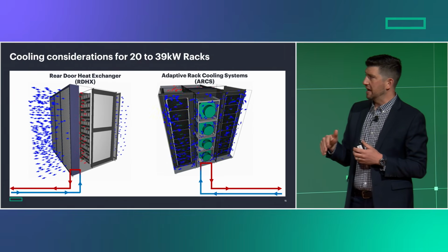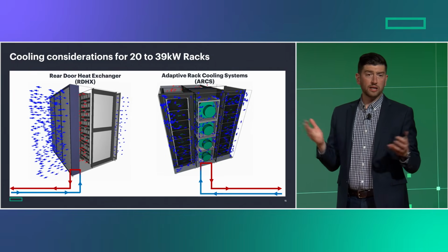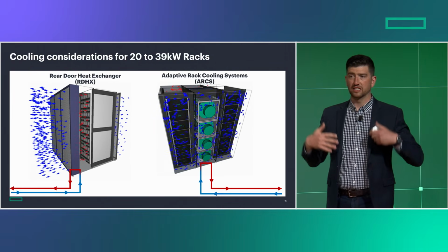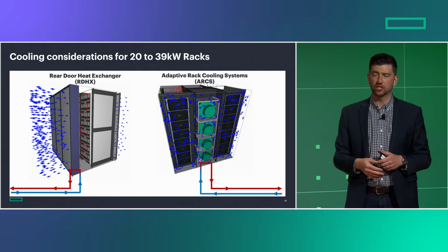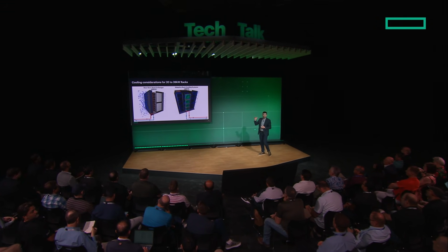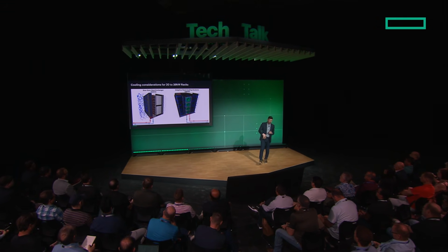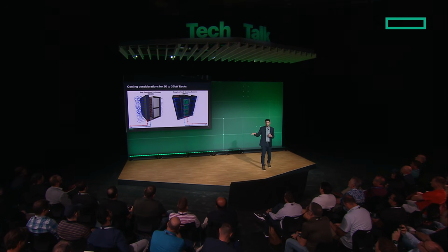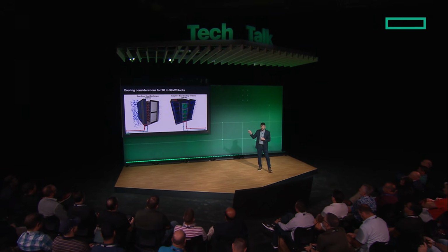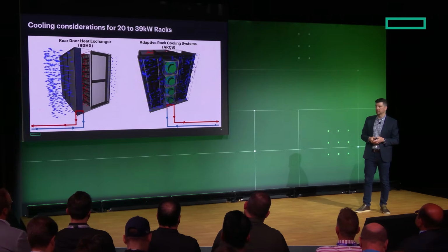So if your data center has thermal issues today, from the HVAC system reaching its limits for air exchange capabilities, this actually brings that air temperature back down. If you ever stood in a data center hot row where rear door heat exchangers are installed, it's like average room neutral temperature coming out—with velocity because fans are assisting it, but not hot at all. That's the purpose of a rear door, alleviating the pressure on the data center.